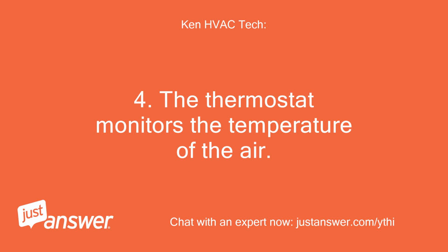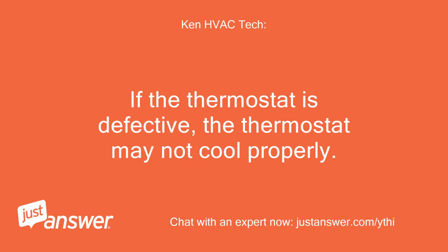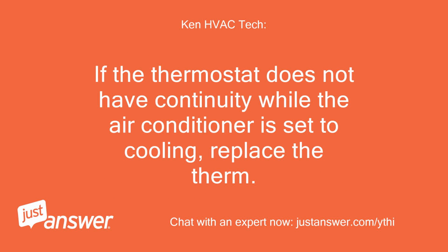4. The thermostat monitors the temperature of the air. When the air temperature rises above a set point, the thermostat activates a switch to provide power to the fan and compressor. If the thermostat is defective, the air conditioner may not cool properly. To determine if the thermostat is defective, set the air conditioner to cooling and then use a multimeter to test the thermostat for continuity. If the thermostat does not have continuity while the air conditioner is set to cooling, replace the thermostat.